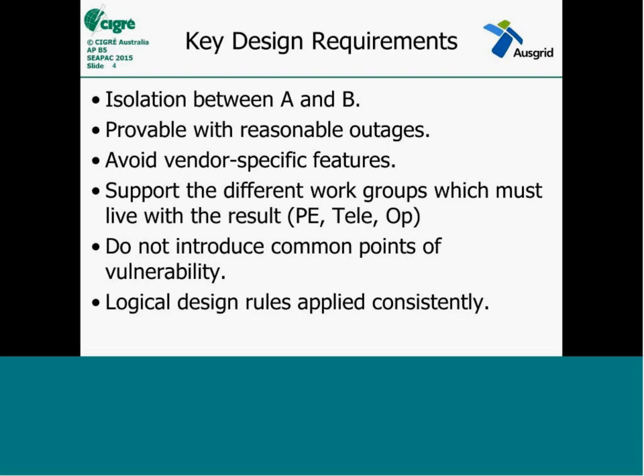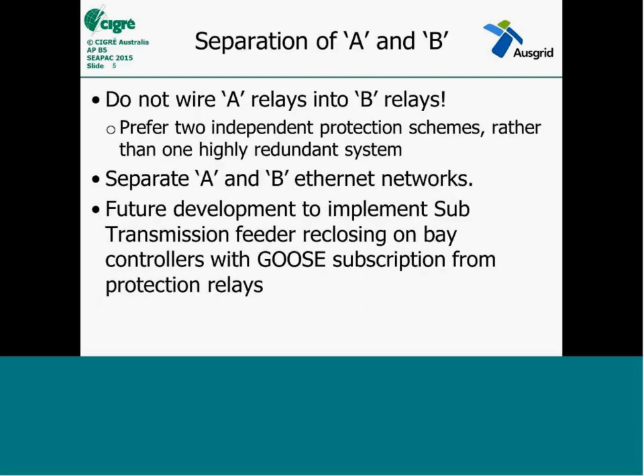Another part is — and this starts touching on the Internet of Things — everyone very quickly starts cross-connecting devices, and our fundamental design was to make sure that didn't happen. The separation of A and B is our big thing in the organisation. We don't wire A-relays into B-relays on separate DC schemes, separate communications networks. We don't run open rings. We now prefer the folded ring with an extra path, so you get a complete outage on one scheme but you know definitely that the other scheme hasn't been impacted. There are more details of that in the paper that was sent with this meeting invite.